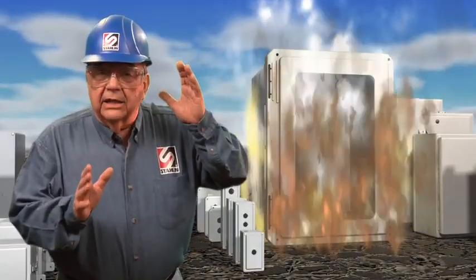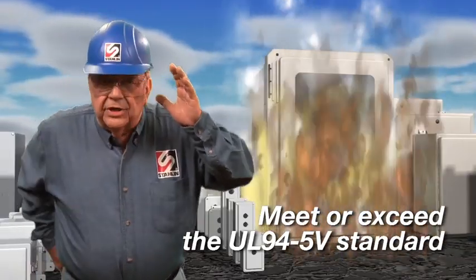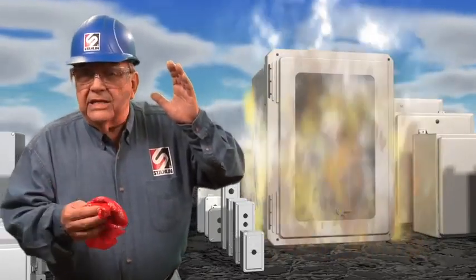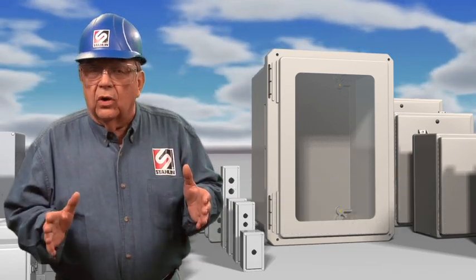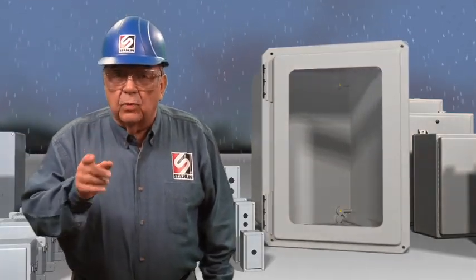Stahlin non-metallic enclosures meet or exceed the UL 94 5V standard, the most stringent flammability verification test in use today. The materials self-extinguish when the flame heat source is removed. Smoke emissions are non-halogenated, meaning no toxic fumes are present when material is burned. While most others perform to UL 94 V0, the UL 94 5V is five times more stringent.